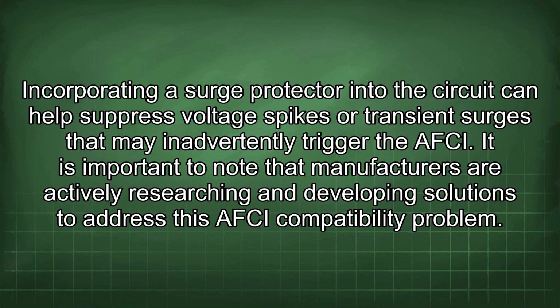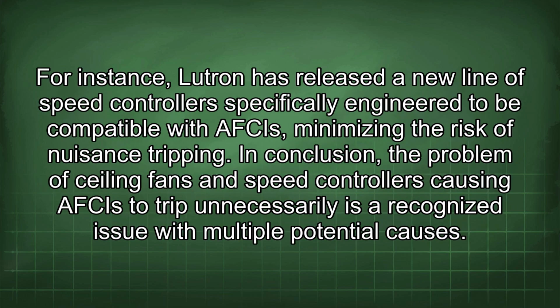It is important to note that manufacturers are actively researching and developing solutions to address this AFCI compatibility problem. For instance, Lutron has released a new line of speed controllers specifically engineered to be compatible with AFCIs, minimizing the risk of nuisance tripping. In conclusion, the problem of ceiling fans and speed controllers causing AFCIs to trip unnecessarily is a recognized issue with multiple potential causes.